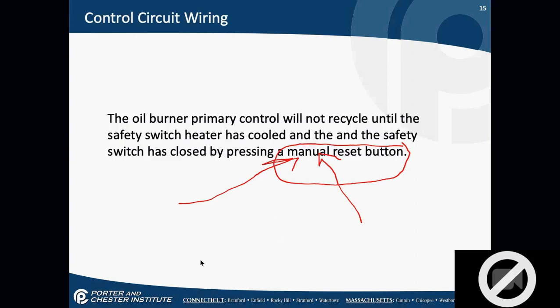I'm going to pull that burner compartment open, and I'm going to check and make sure that there's not a lot of unburned fuel in there before I do anything else. Because the second I get a flame on that burner, even if I say, oh, I'll just check it and see if it runs, and I'll shut it off real quick and then check inside. Nope, too late. Once that oil catches, once those vapors catch, I have actually seen a boiler lift about 6 inches off the ground. A big, heavy steel boiler.